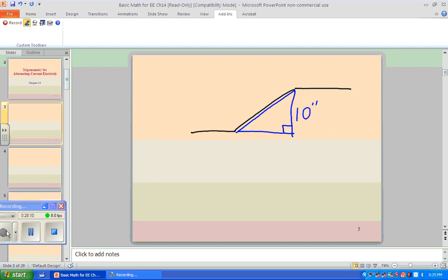All right? Now, we know that we're going to use one of a couple of different angles because we're familiar with them. Now, if we bend this thing up, let's say 30 degrees, then we know that we're going to have to bend this conduit back down. It would have been up here. We're going to bend it back down 30 degrees at this point, right? And this is going to be bent at this point. What is that distance? What do we call this distance between those two marks that we're going to put on the pipe to bend them? We call that the hypotenuse.